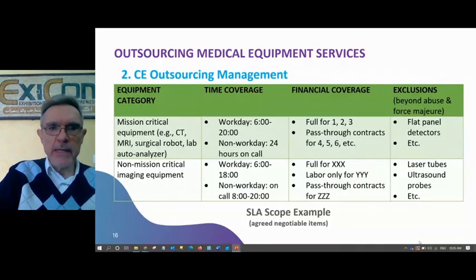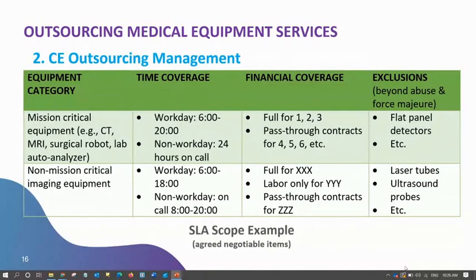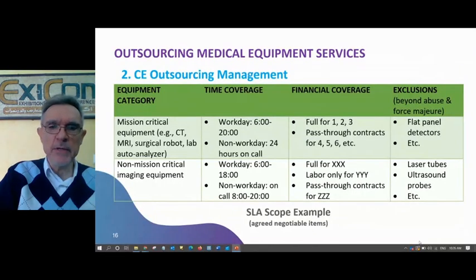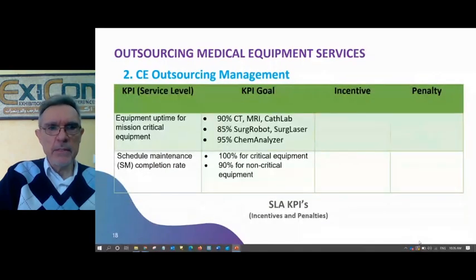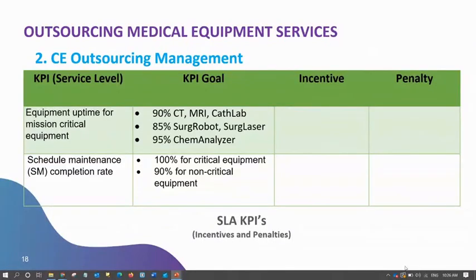In terms of non-critical biomedical equipment, it is a similar thing, and part of the exclusions, for example, like parts for flexible endoscopes, and non-mission critical lab equipment, also from 6, for example, till 18, and during non-work days from 8 till 20, and exclusion, for example, calibration reagents. So all of these items should be agreed upon and negotiated with the service provider. Another KPI is the uptime for the critical mission equipment, for example, 90% for CT MRI, 85% for the robots, lasers, 95% for the chemistry analyzers. And for the scheduled PM, it should be 100% for critical equipment, 90% for non-critical equipment.